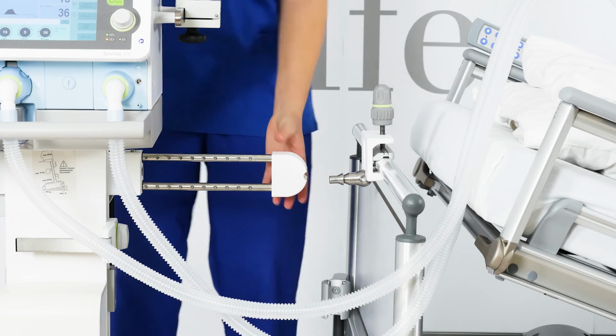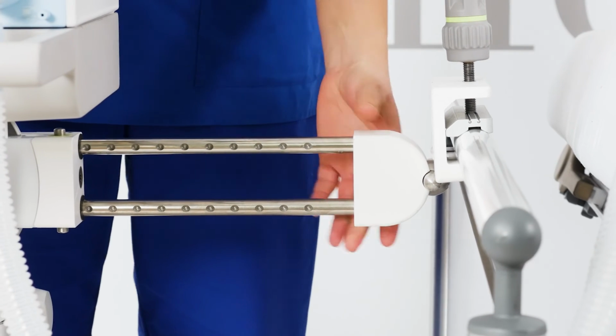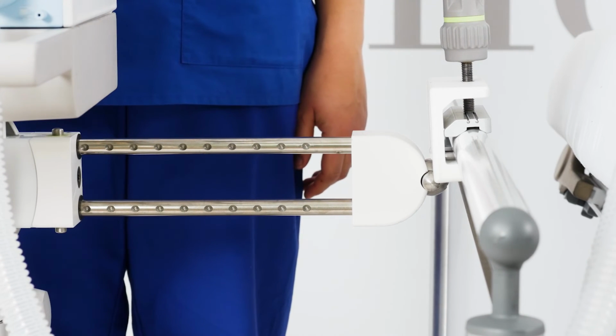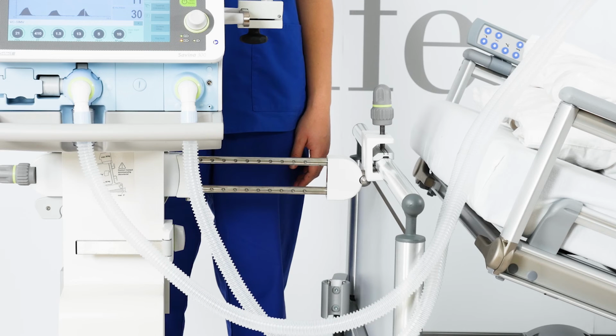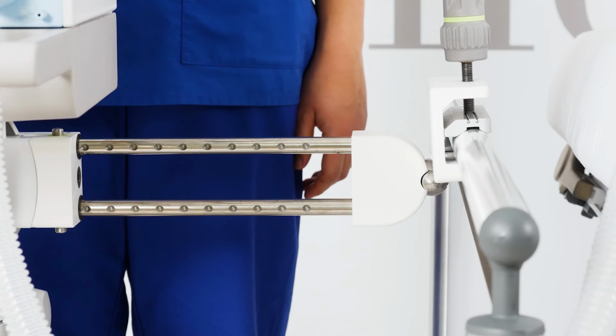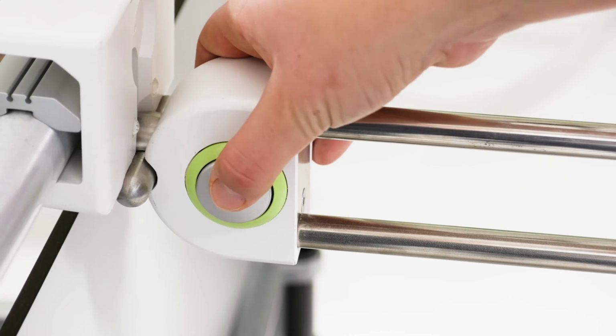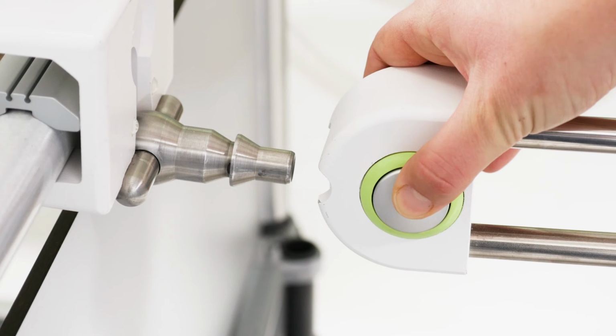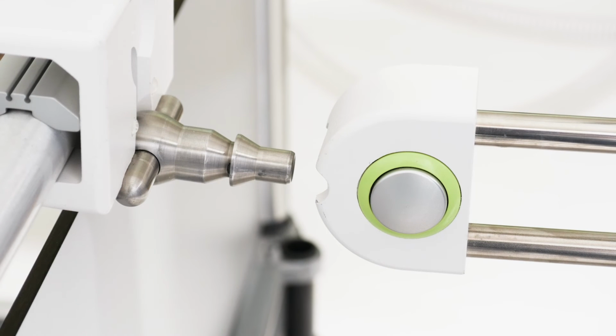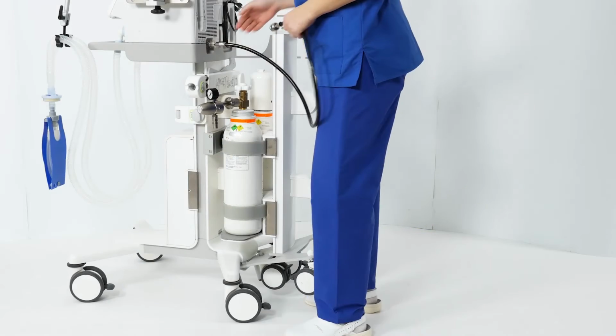Adjust the distance between the device and the bed. Press the release button for this purpose. Push the device towards the bed until the coupling connector engages audibly in the coupling head of the device side coupling part. For uncoupling the device and the bed, press and hold the release button on the device side coupling part. Detach the device from the bed simultaneously.